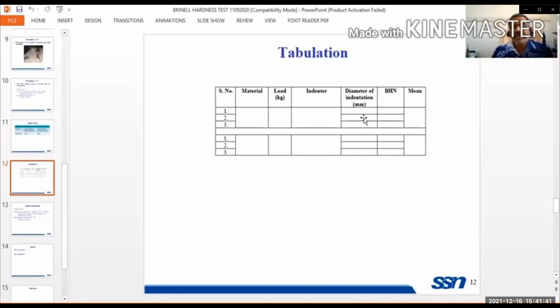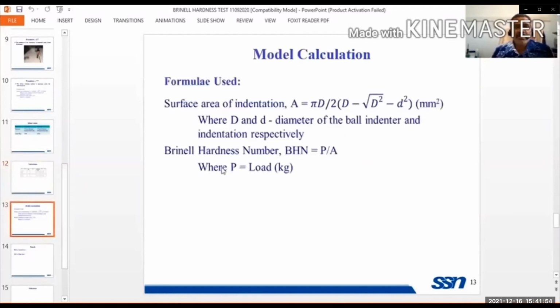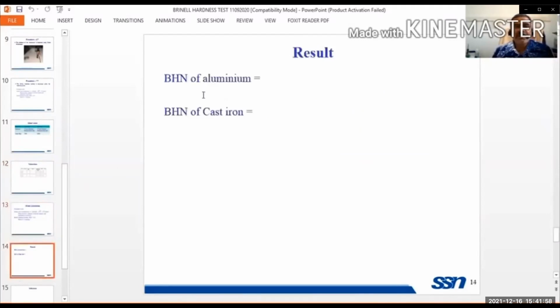You enter the diameter, then you enter the hardness value. The hardness value you will get from the calculation. Then you have to write the mean. We have taken only one reading, so you write that reading. This is the equation for calculation. Finally, in the results you write the Brinell hardness number of aluminum and the Brinell hardness number of cast iron.